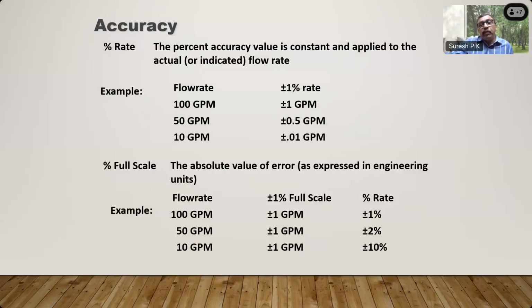Then another term which is very frequently misused is percentage full scale. I'll show you the example. The percentage accuracy value is constant and applied to the actual flow rate. Suppose the flow meter is 1% accurate: at 100 GPM, the error will be 1 GPM. At 50 GPM, the error will be 0.5 GPM. That is 1% accurate. At 1 GPM, it will be 0.01 GPM. But that is in absolute value.